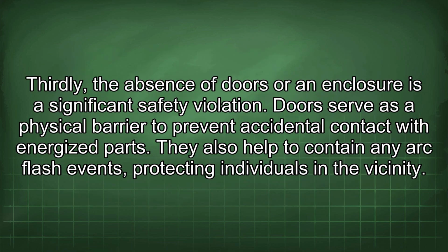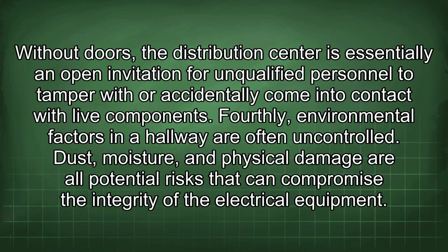Thirdly, the absence of doors or an enclosure is a significant safety violation. Doors serve as a physical barrier to prevent accidental contact with energized parts. They also help to contain any arc flash events, protecting individuals in the vicinity. Without doors, a distribution center is essentially an open invitation for unqualified personnel to tamper with or accidentally come into contact with live components.